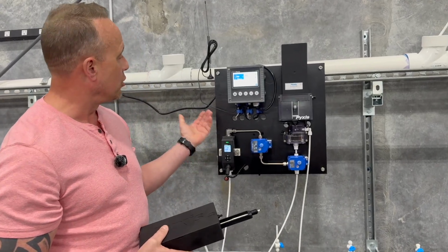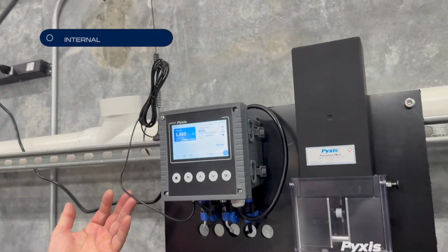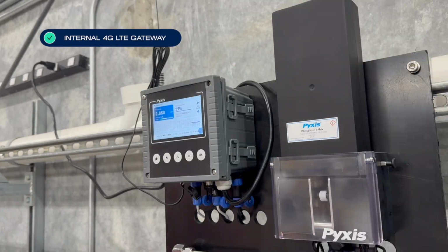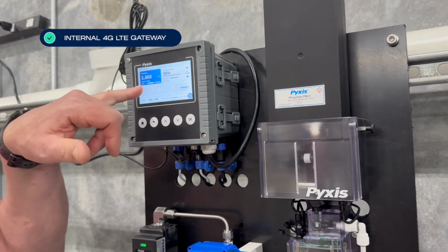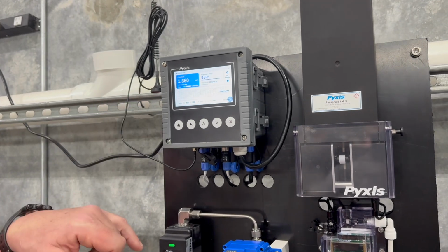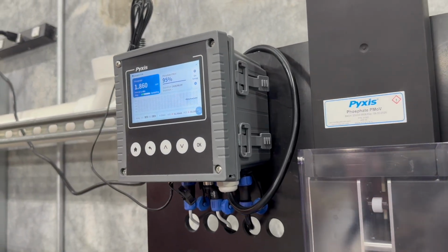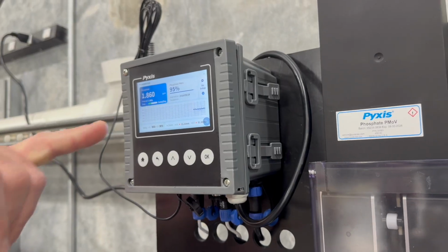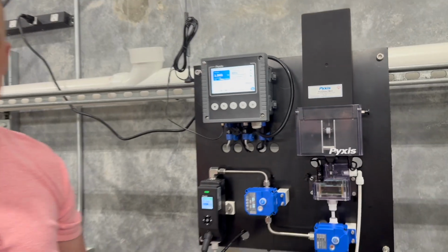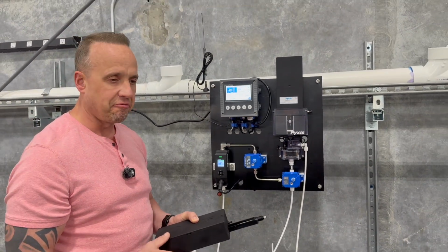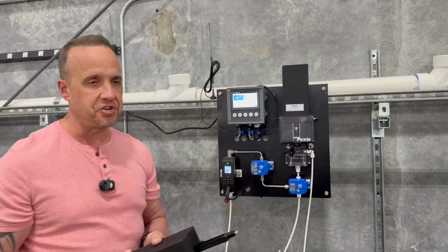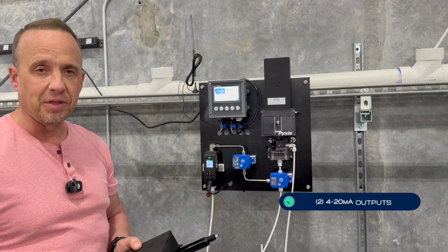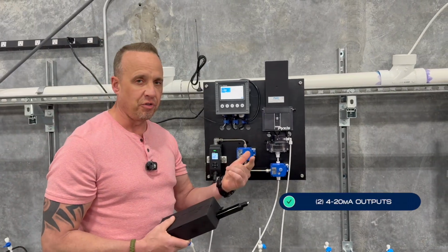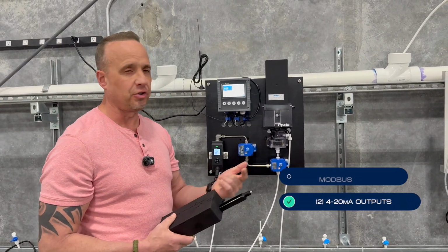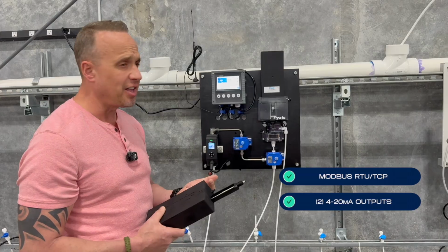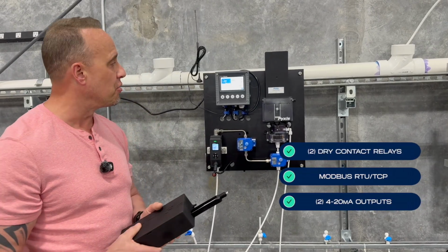The HMI includes a digital 4G gateway, which is deactivated with a global SIM card, can be activated upon request. You'll have a live reading of the actual previous test result, and you'll have a graphical display of the test value as the tests occur, as well as a remaining inventory volume within the cartridge. So every time you change the cartridge out, you'll get a fresh inventory volume display on the HMI. The unit offers two 4 to 20 milliamp outputs, one for the reading and one for the reagent inventory. Offers Modbus RTU and Modbus TCP, and it has 2 dry contact relays which can be programmed for alarming.